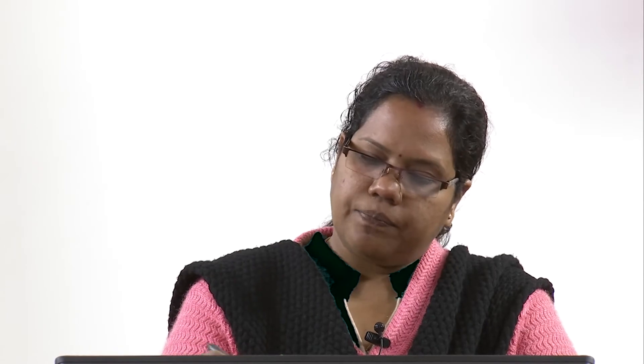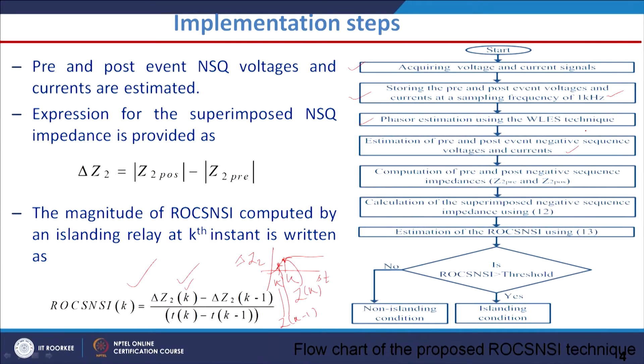The steps are: acquire voltage and current signals at the DER terminal and store pre- and post-event voltage and current data sampled at 1 kHz. Next, estimate the phasor using the weighted least error square (WLES) technique. Then calculate the pre- and post-event ΔZ2, and finally the rate of change of the impedance.